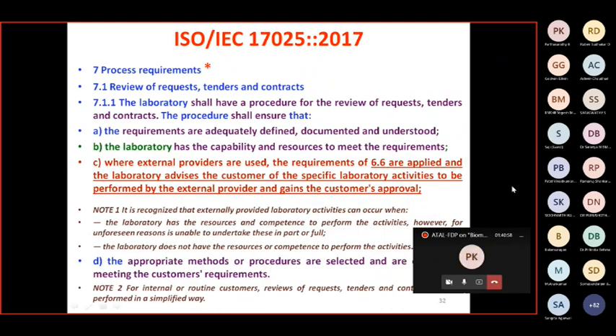So now we come to the process. As I said, first, do we understand what the customer communicates to us clearly? If he gives an instrument and says calibrate and give the calibration report, then you cannot just take that order and start calibrating. Once you finish calibrating and send it to him, he may say, I didn't want it against this standard, I wanted calibration for the other standard.